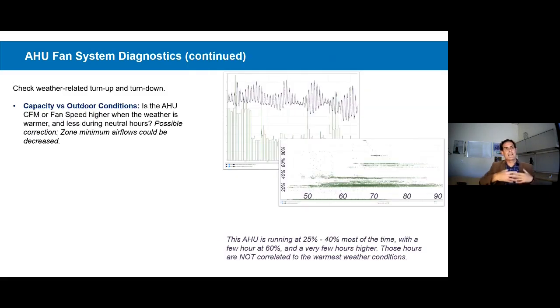One thing that we can do is we can take a variable like fan speed or fan capacity and plot it against outside air temperature. That's what you see in this smaller picture. We have outside air temperature on the x-axis and then that fan speed on the y-axis. So notice how the data is not a bell curve. It's not normally distributed. It's a multi-modal distribution. We have a big node at 25%, which means regardless of temperature, whether it's 50 degrees outside or 90 degrees outside, we're spending a lot of time at 25% fan speed. Then we have this second weaker node up around 40%. And then we have these even weaker nodes above that, a weak node up at like 50 or 60%, and another very weak node up at 75%.